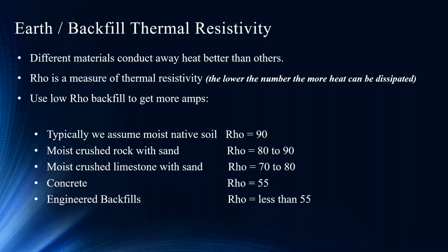RHO is an indicator of the heat transfer capability of a uniform filler through conduction, and it is expressed in degree centigrade centimeters per watt. In North America, though, the RHO values for soil in different parts of the country can be as low as 60 in wet soils, up to 120 in very rocky or dry and sandy areas.